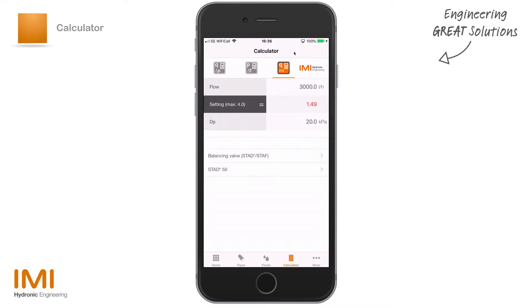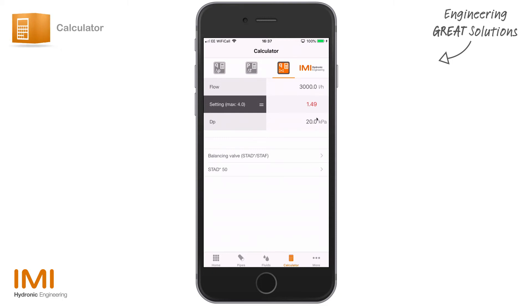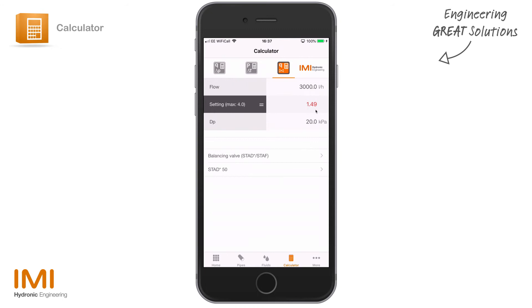The third section is the flow setting and delta P component of the calculator. This allows us to pre-determine what the setting is going to be on a given valve — particularly for variable orifice type valves where you're looking to pre-determine the setting at a given pressure drop for a given flow rate. You can see the calculator has pulled through our 3,000 liters per hour from our previous calculation, and also our 20 kPa delta P selection. We can determine here what our valve type is — at the moment it's showing a STAD, and that STAD is a DN50 version.